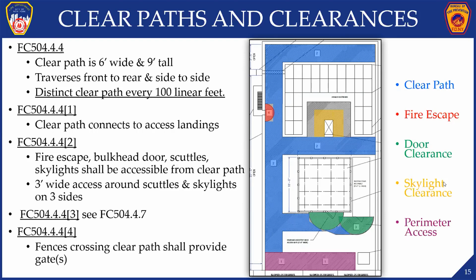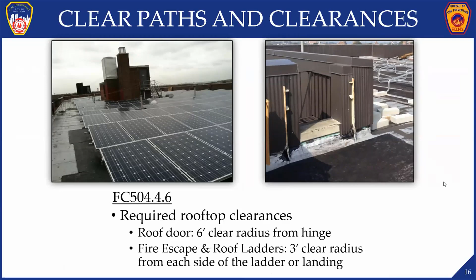The clearance around the rooftop doors must be 6 feet clear radius from the hinge of the door. So you take it from the hinge, 180 degrees, that's 6 feet, that is your clearance around the door. Fire escapes and roof ladders need 3 feet on either side of the ladder or on the other side of the landing opening.